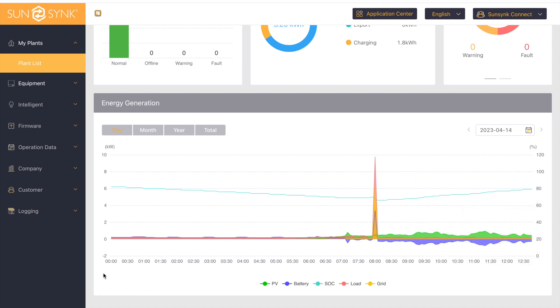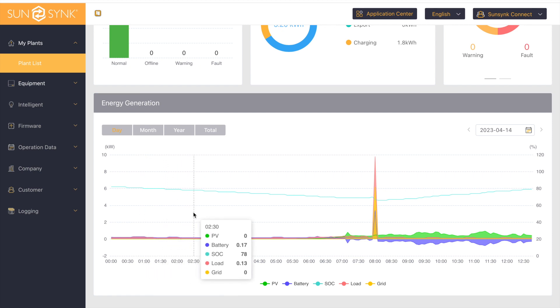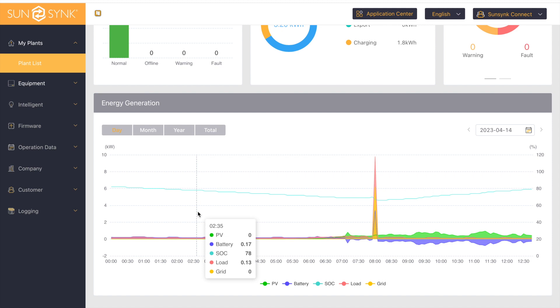On the left hand side, this is showing you in kilowatts. So as we go along, here for example, at 2:35 am, my state of charge was 78%, my load was 130 watts, I was pulling nothing from the grid, and I was providing the load and the inverter from the battery.